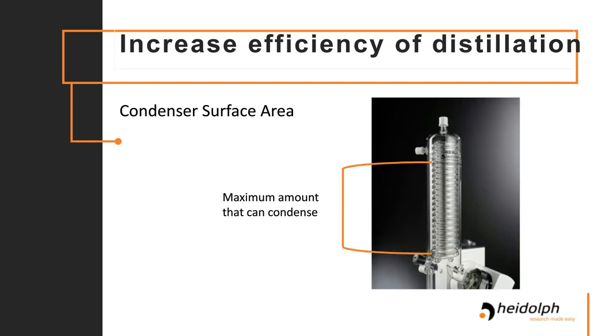So the first limit is the surface area of your condenser. You can't evaporate more than your condenser can condense. Otherwise, you're just going to be sucking all of that solvent, or that stuff that you're boiling off, straight to your vacuum pump without actually condensing it back into your receiving flask. Another important point is that you're not actually using the entire size of your condenser. You want to be going about 3/4 of the way up. Any further than that, and you're also risking pulling some solvent through your vacuum pump and losing it instead of retaining it.